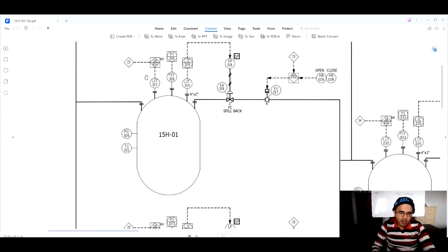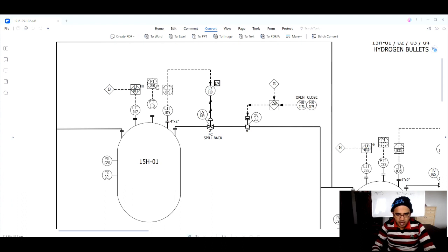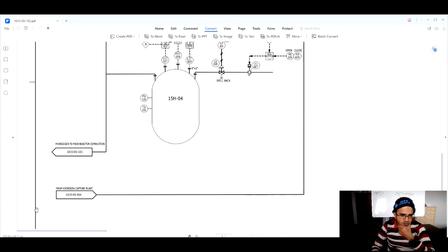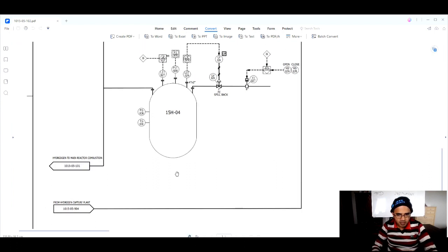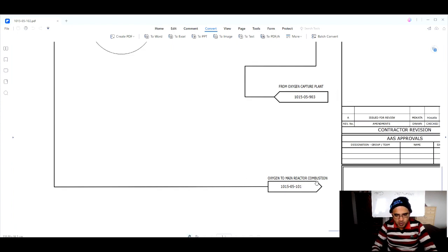One level transmitter is for the safety system — this diamond symbol means it is for the safety system. A circle inscribed in a rectangle or square means it belongs to the distributed control system (DCS). Hydrogen comes from the hydrogen capture plant and goes to the main reactor combustion. Similarly, oxygen comes from the oxygen capture plant and goes to the main reactor combustion.